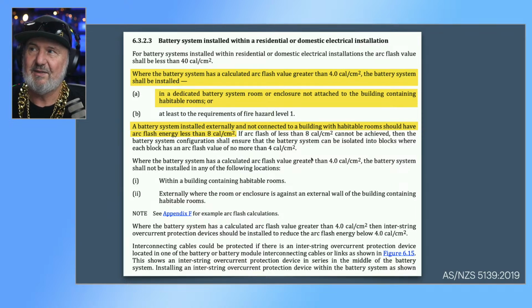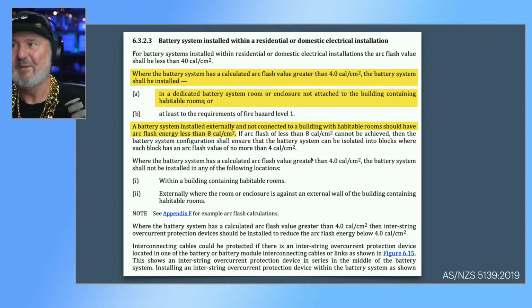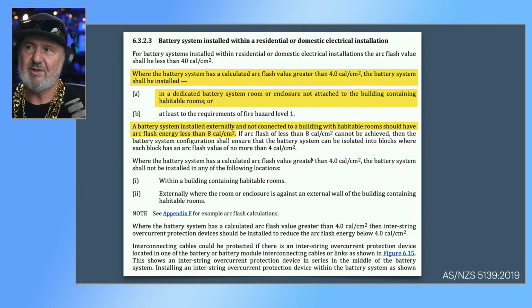But where the battery system has an arc flash value greater than 4 cal, the battery system shall be installed in a dedicated battery room or enclosure not attached to the building containing habitable rooms. So you really want to get below 4 cal, and you need to meet the requirements of fire hazard level 1, which is another topic, which I've probably also covered in the previous Toolbox Tech Talk. If the battery system is installed externally and not connected to the building, you can actually go up to arc flash energy levels of up to 8 cal per square centimetre.